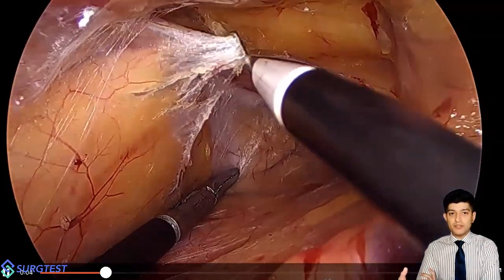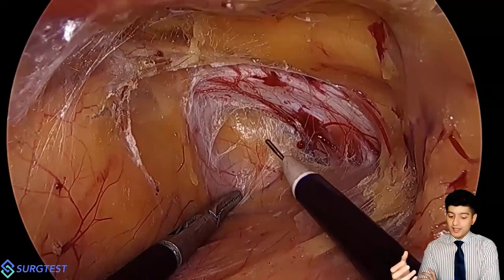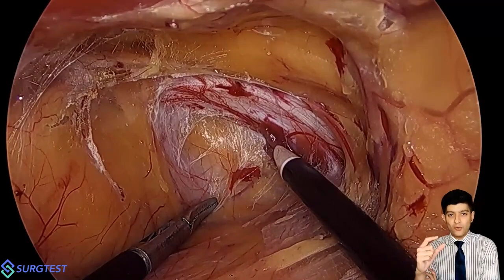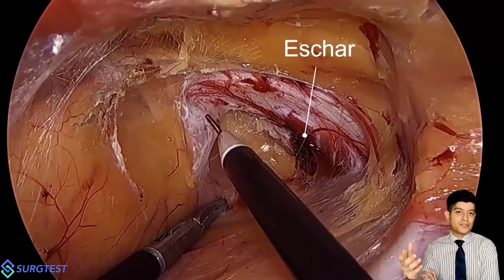There's a reason for that. The coagulating current has an extremely high voltage, and that voltage ends up increasing the tissue temperatures to 200 degrees and beyond. That is the point that produces carbonization. In comparison, wherever I'm using cut, the low voltage continuous waveform current, low voltage being the keyword, just gets the tissue temperatures up to around 100 degrees, vaporization. So tissues are getting divided, the blood vessels are getting nicely coagulated, and I have a clean surgical field except for that one filthy part where I ended up using a coagulating current, correct?